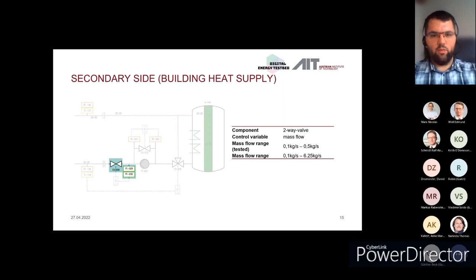So the last value we want to set is the flow temperature, and this will be controlled by the district heating substation. You can see it here again, a really reduced scheme of it. There are some more components, but they are not necessary yet for us. So we can see here, for example, a heat exchanger with a design point with this design thermal power of 42 kilowatts, and we got them at an inlet temperature of 90 degrees and outlet temperature of 60 degrees on the primary side, and on the secondary side there were set temperatures of 55 degrees inlet temperature and 75 degrees outlet temperature.